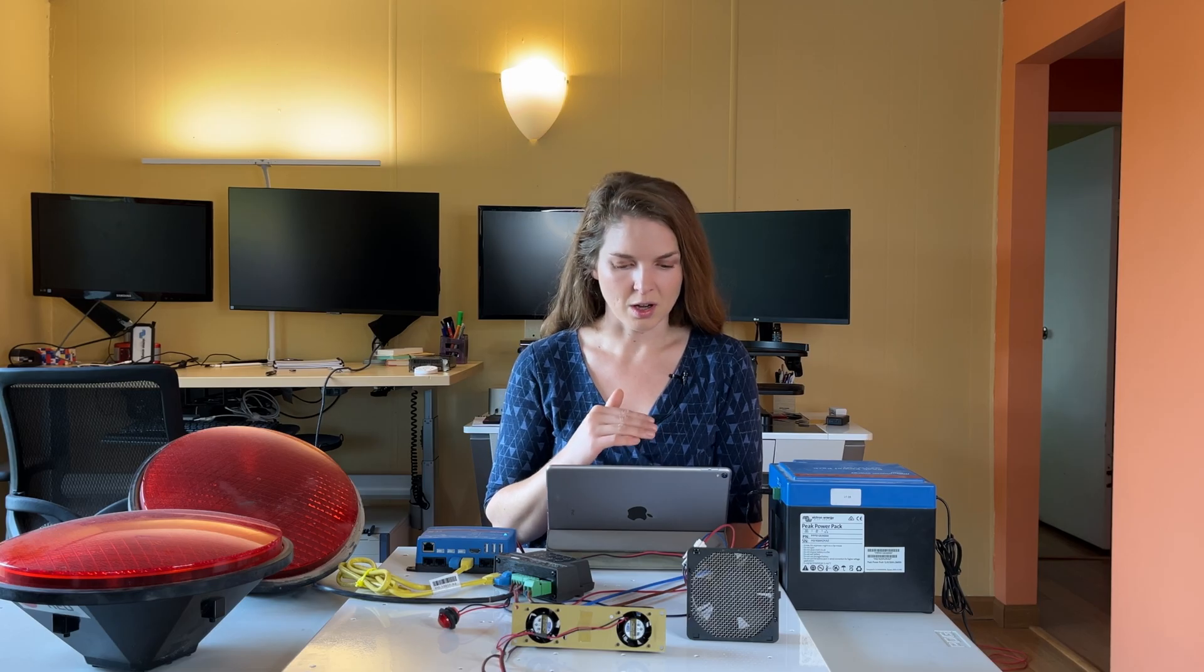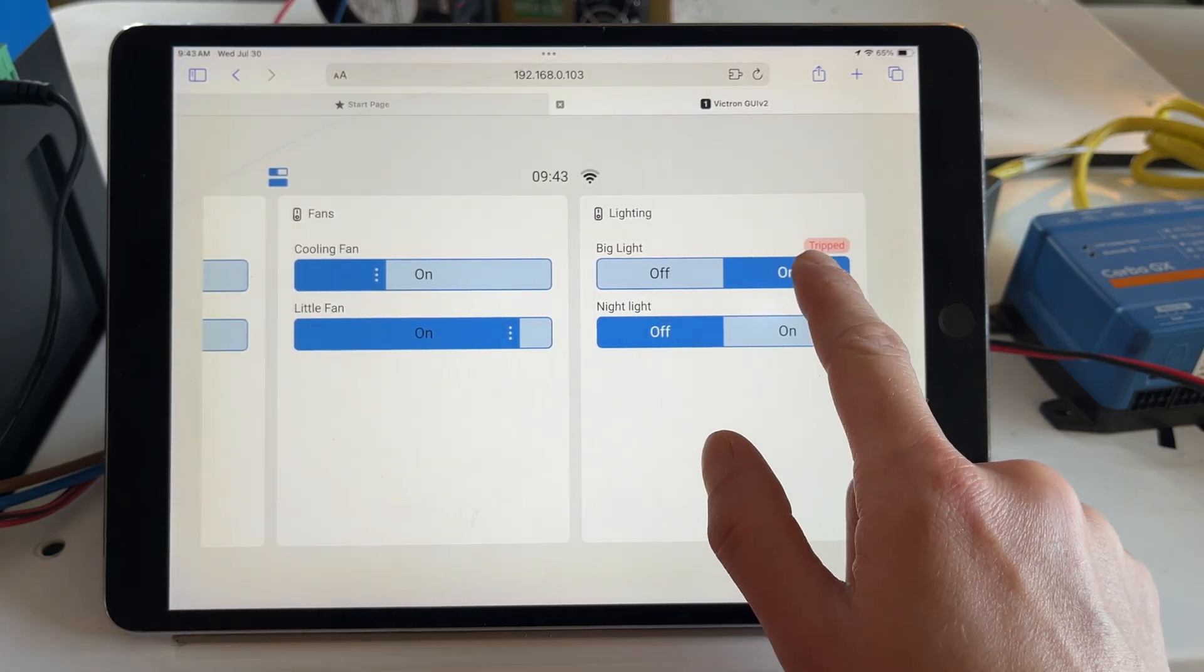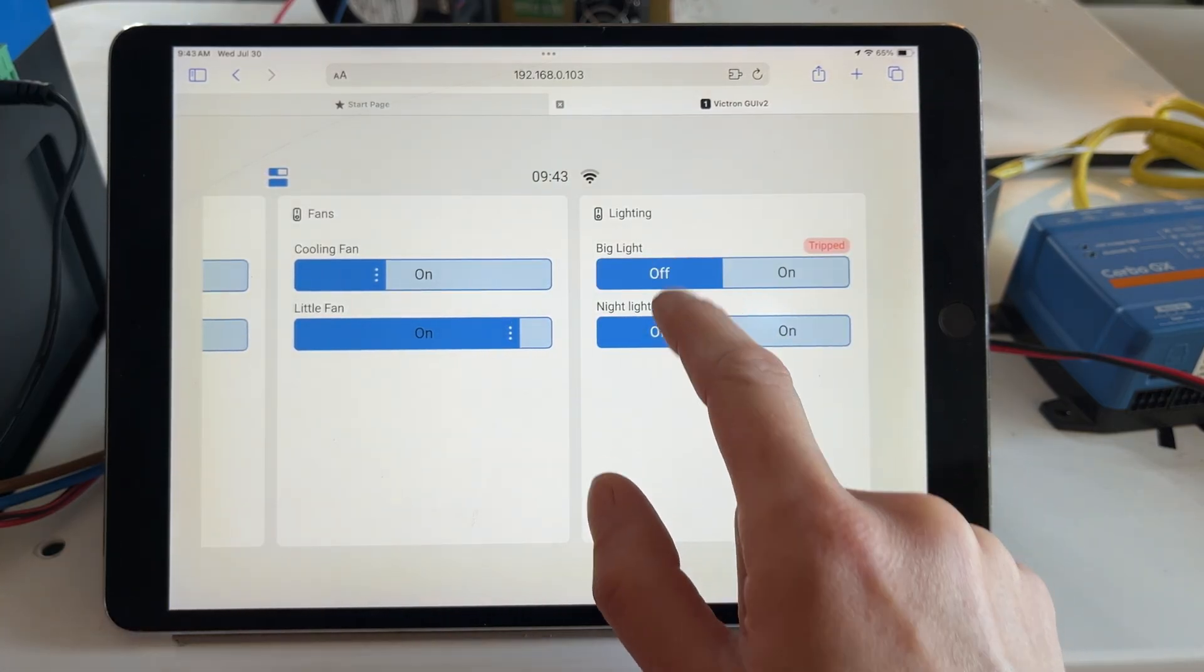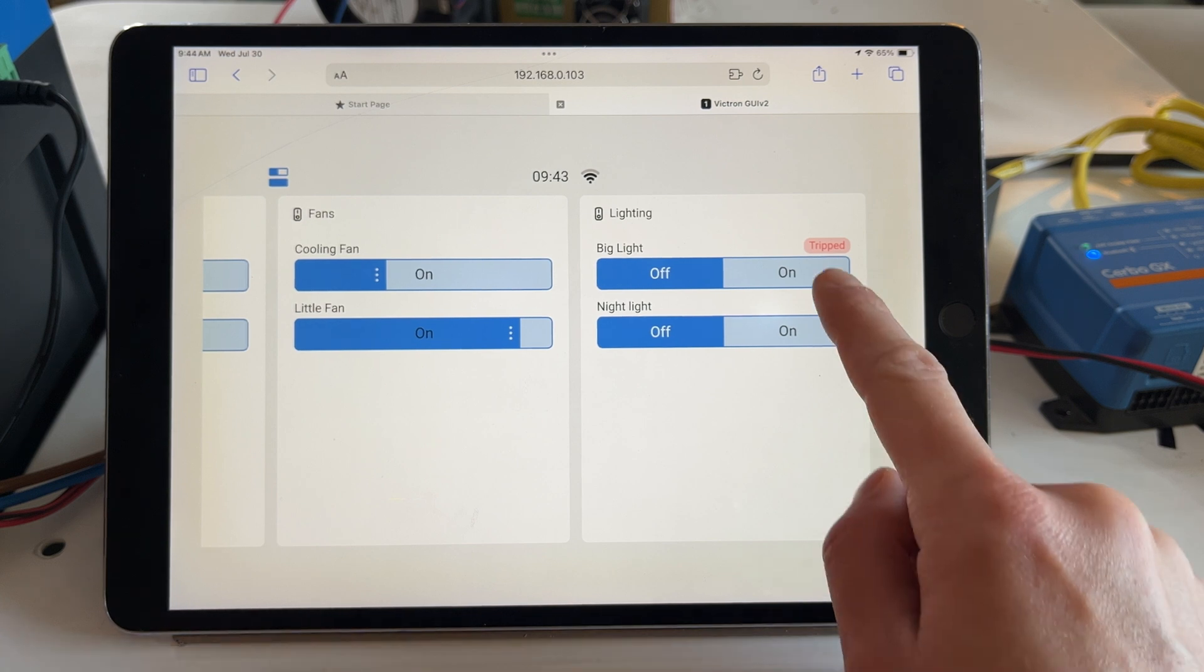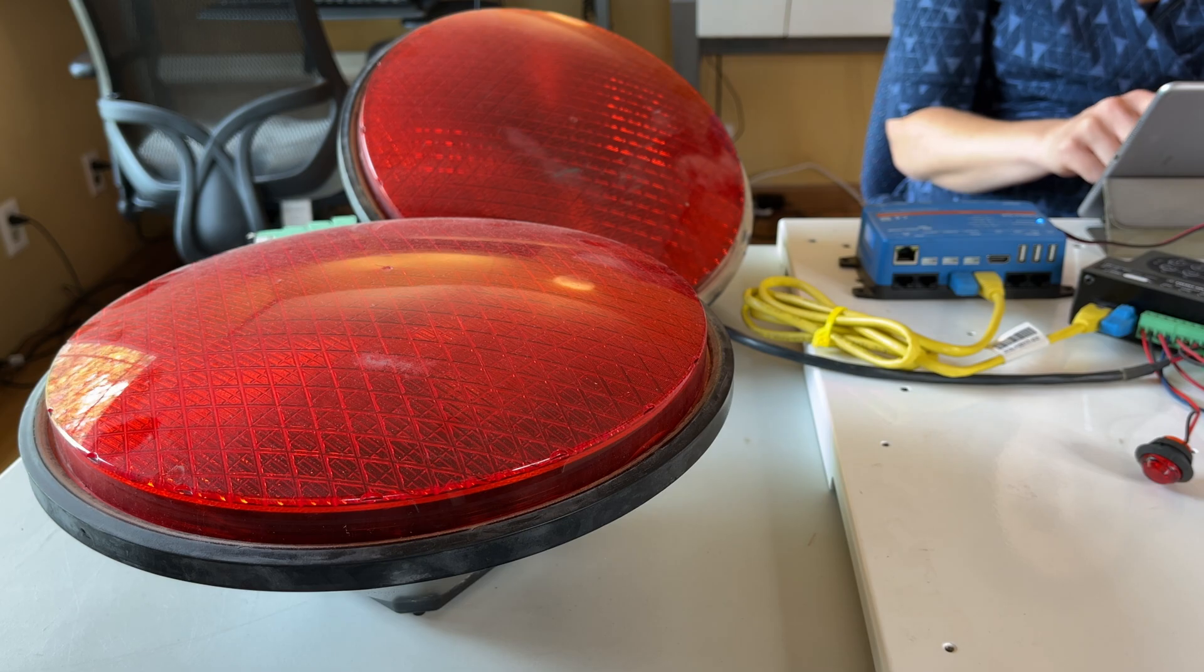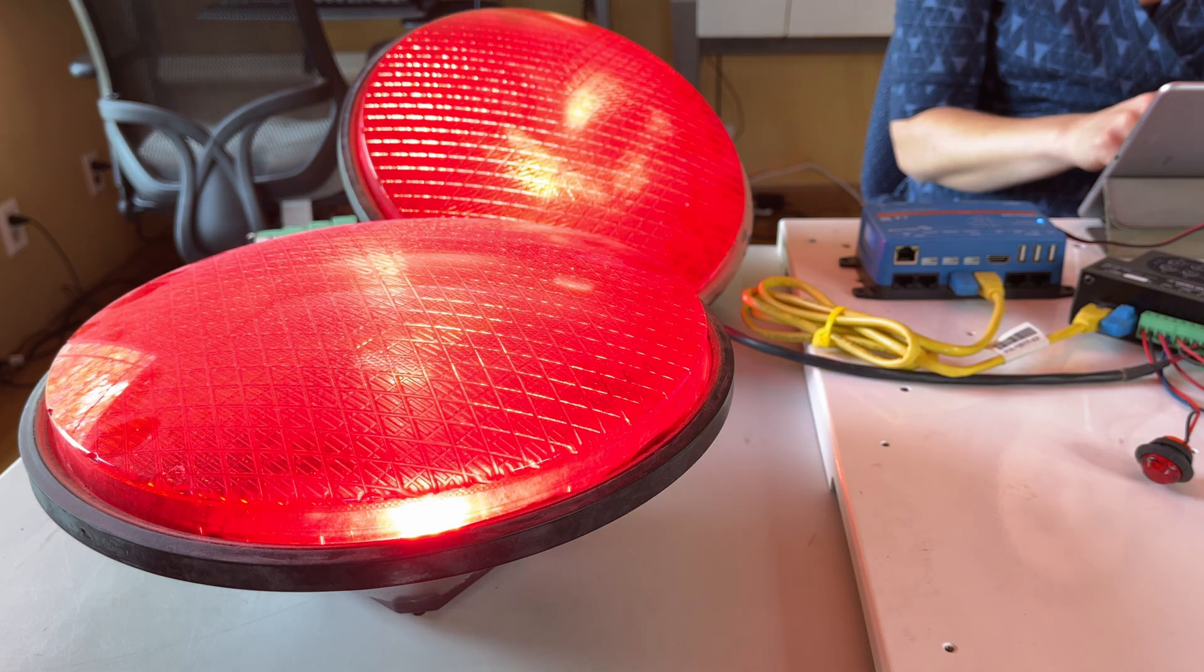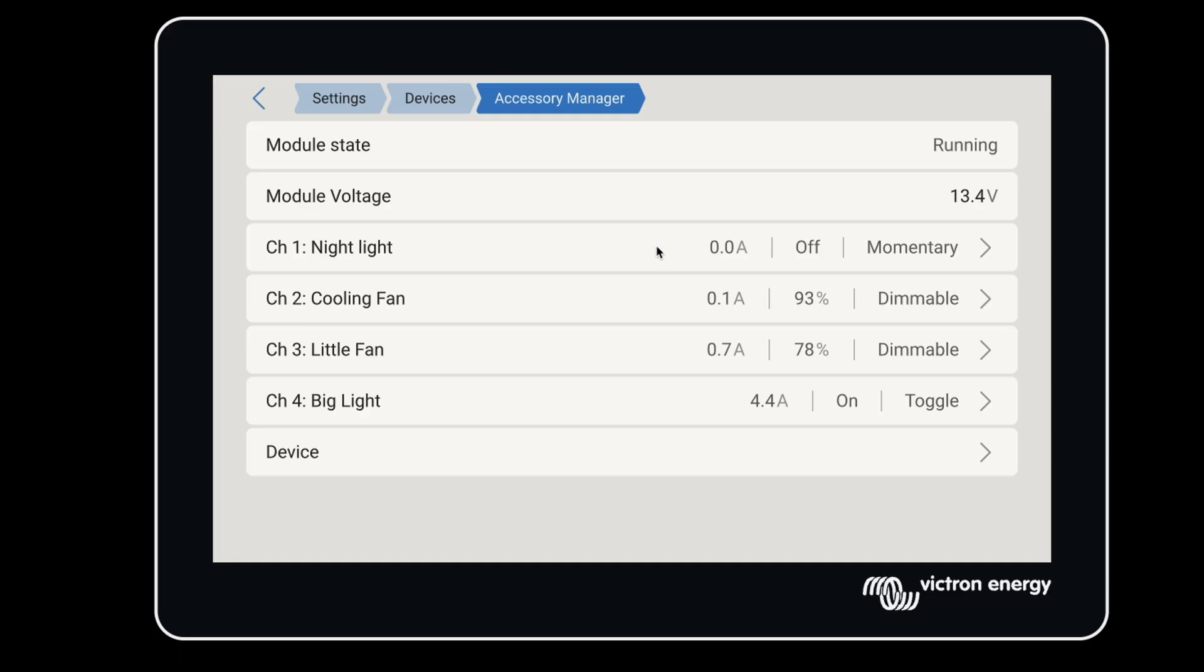Each channel can be switched off or on from the touch screen in order to reset it remotely if we overload the circuit, which is really helpful. You can feed the smart switch with different voltages and this input voltage is what is powering those loads. And because we're fused digitally, we don't need another panel with fuses. We have circuit overload protection and we're able to monitor how many amps are going through.